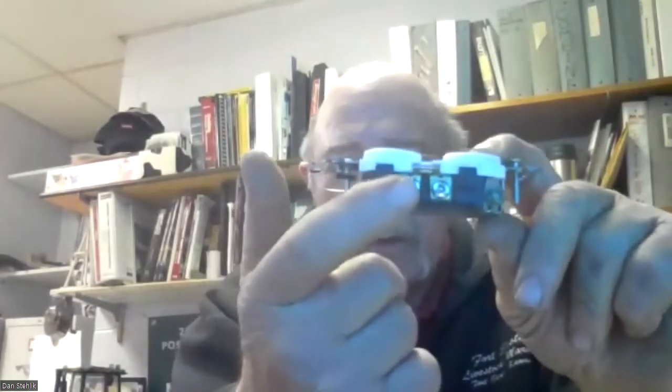Same way in the second box, we have 2 gold screws, so a black wire in and a black wire out. And on the silver screws, a white wire in, white wire out. And again, we're going to wire nut the grounds. We're not going to fasten them to the box like you would in actual wiring.